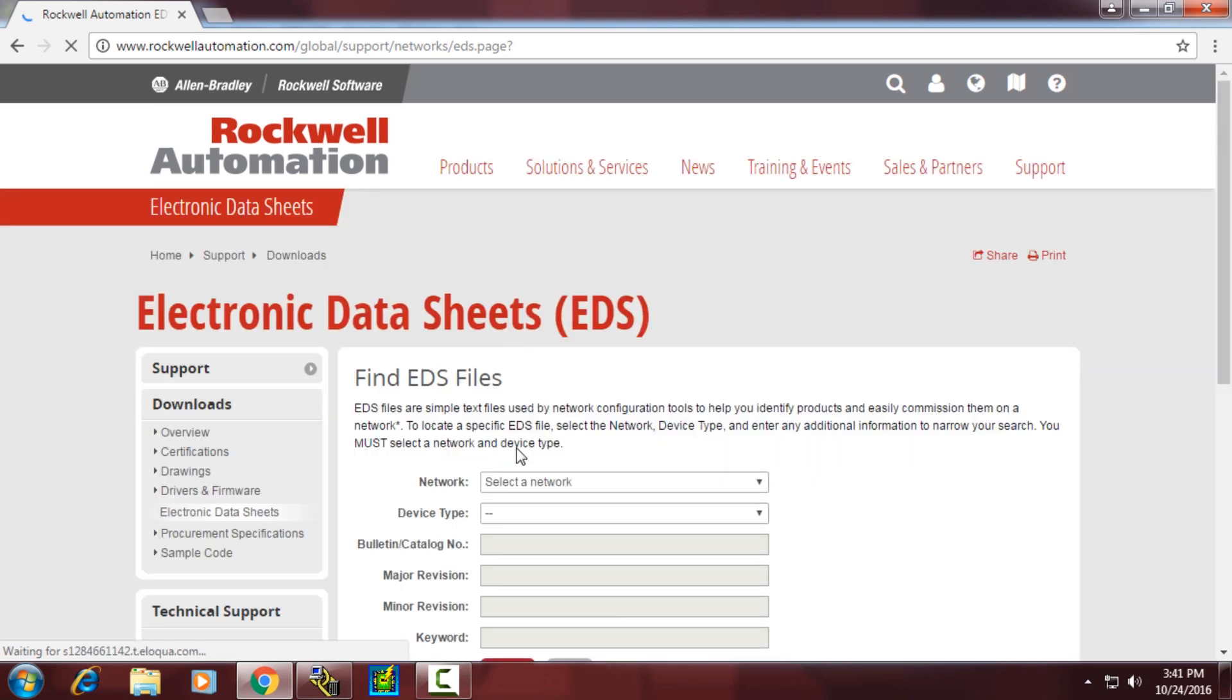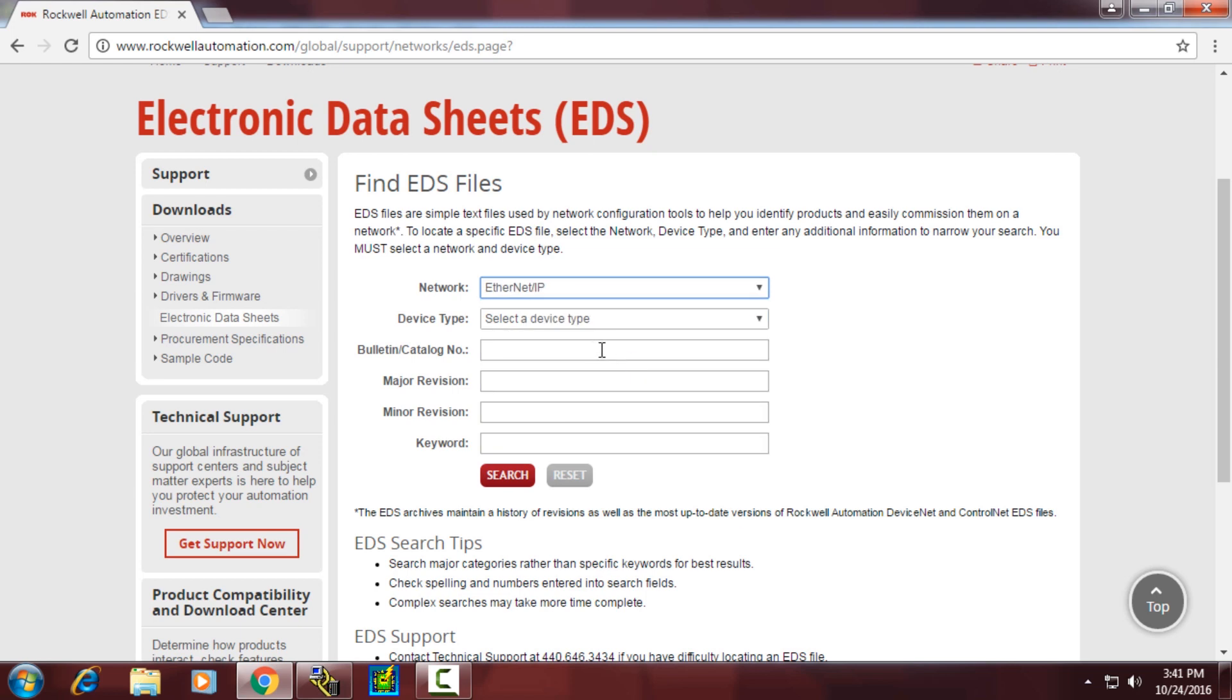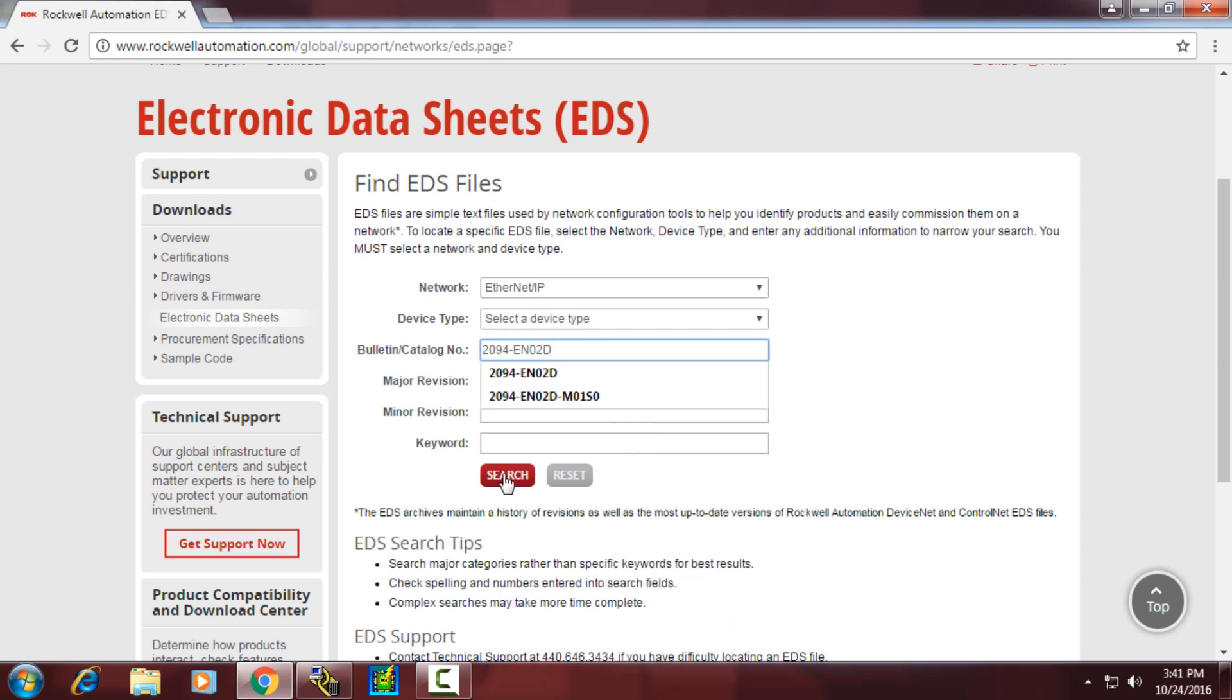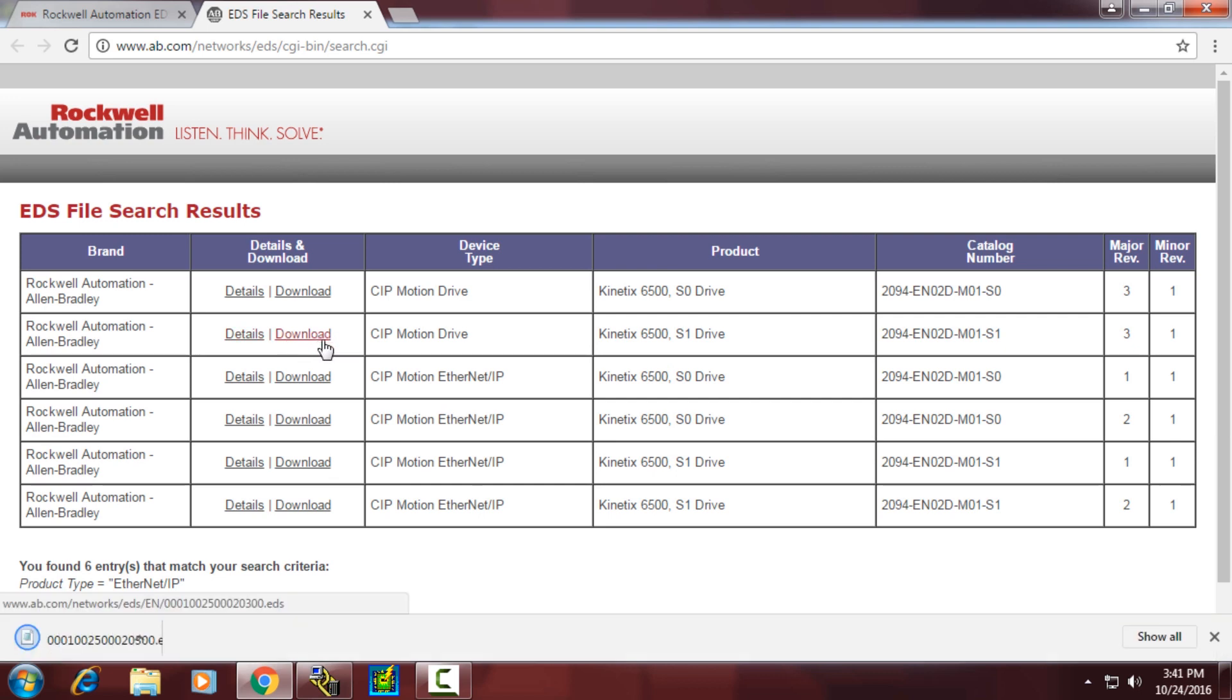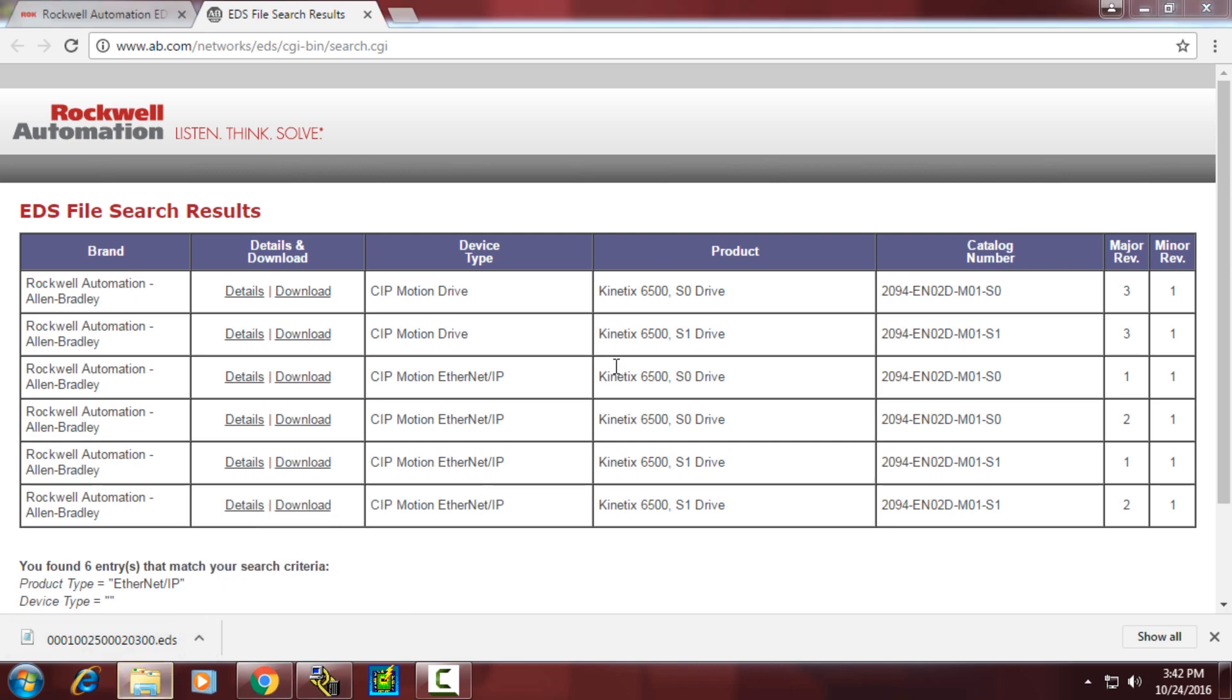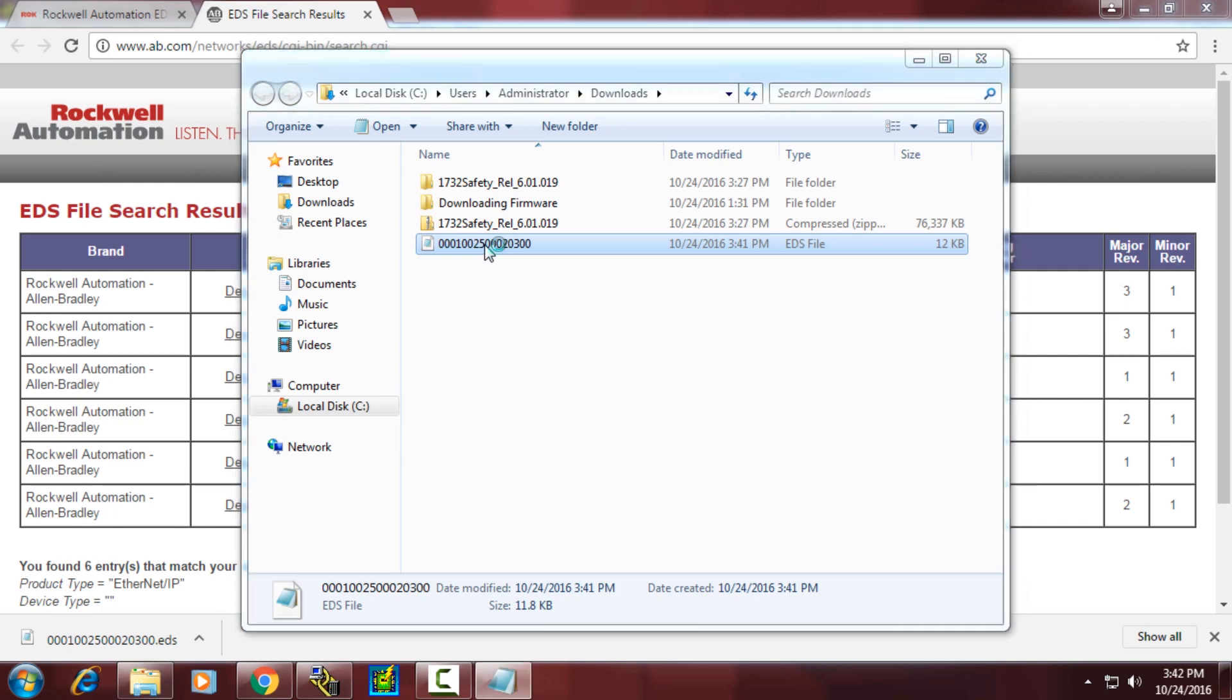We'll select EDS files, choose an Ethernet IP network, and introduce the catalog number for the Kinetix 6500 that we're looking for. We'll need to remember that we were looking for the S1 version at revision 3.1 firmware. We'll choose to download the EDS file, which will download very quickly because it is just a text description. I'll show you the contents of that file.